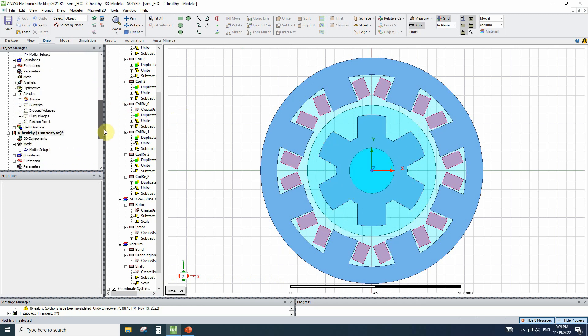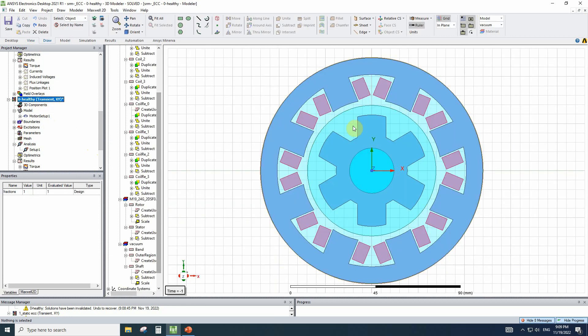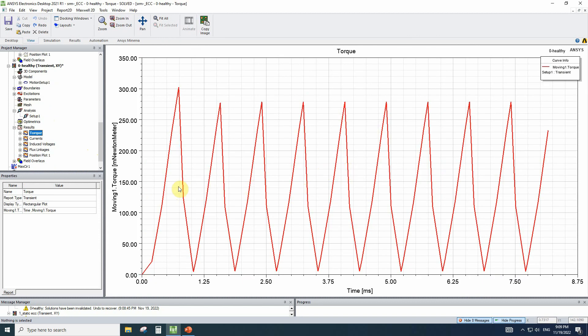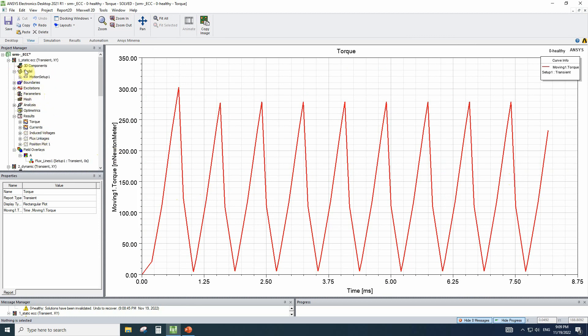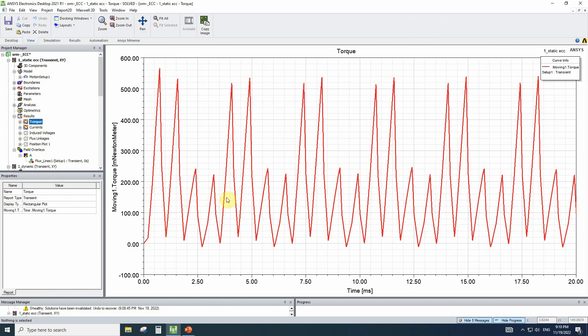Let's see the result of a healthy motor. Here we have a healthy motor — the values are not perfect because we have a very big air gap, but you can see the torque has uniform values. In the static simulation, we move the stator while the band and the rotor have the same center. In this simulation, the produced torque is not uniform — we have some patterns in the electromagnetic torque. These are not perfectly precise results, but notice that we are simulating an exaggerated air gap.